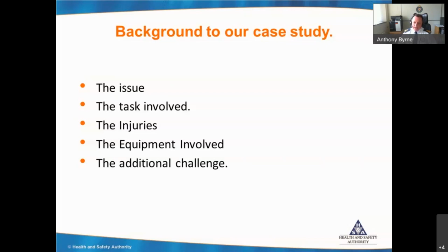But it soon became identified by crews working on the road that there was a high risk because of the weight of the monitor, which was 15 kgs compared to our old monitor in the southeast, the Philips MRX, which is 10 kgs. Its position within the ambulance itself was across the patient from the patient center. As I said, I will show you in the slides a picture of the monitor position, which meant that the practitioner had to bend over, release a catch, pull it up, and then lift this 15 kg monitor out.